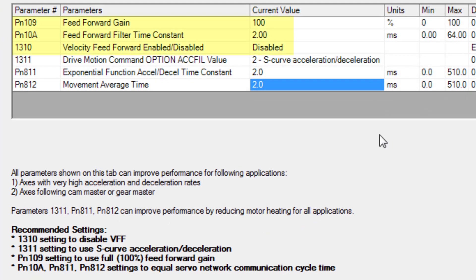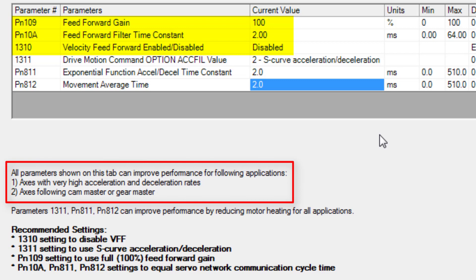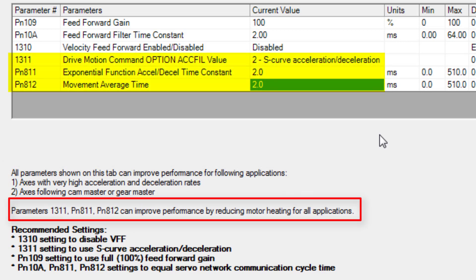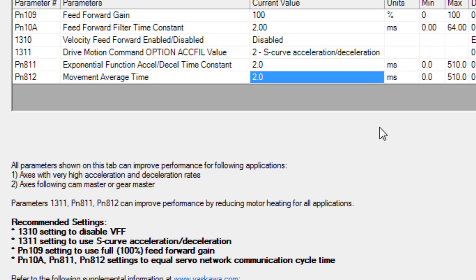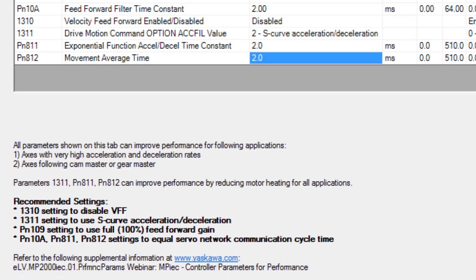So why bother doing this? Feedforward helps reduce position error, especially in applications with high acceleration rates or those following a cam or gear master, when the position error must be extremely low. The other parameters help reduce torque ripple and motor heating. There is a recorded webinar on our website that discusses this in detail, but let me make a summary here.